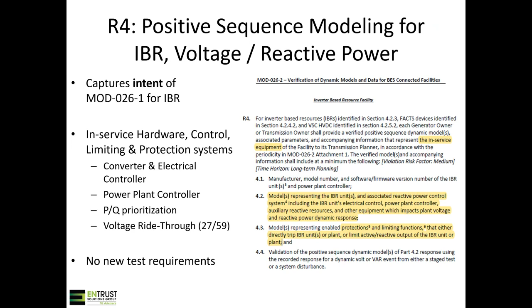You do a step test on the plant controller and take that back. Really, you need manufacturer's information for all of the converter electrical controls. Anything down at the IBR unit level, right? Your wind turbine inverter. That's information that really has to come from the OEM once the plant is in service.